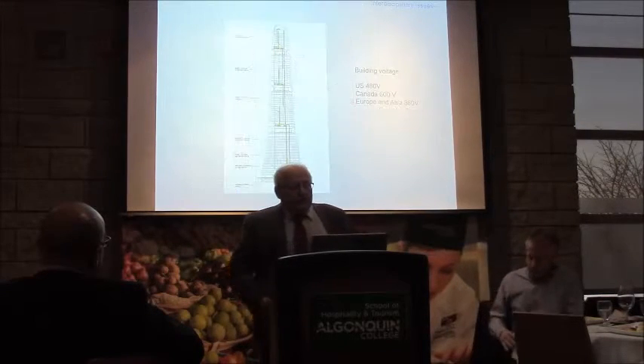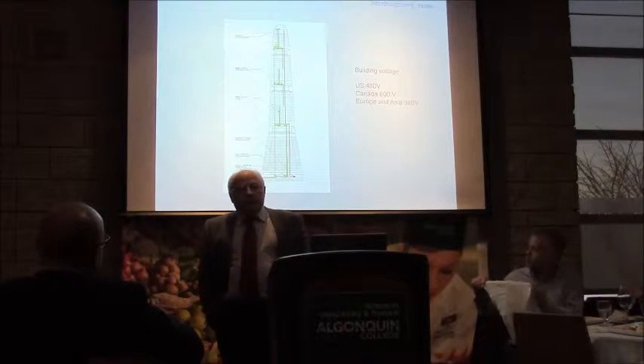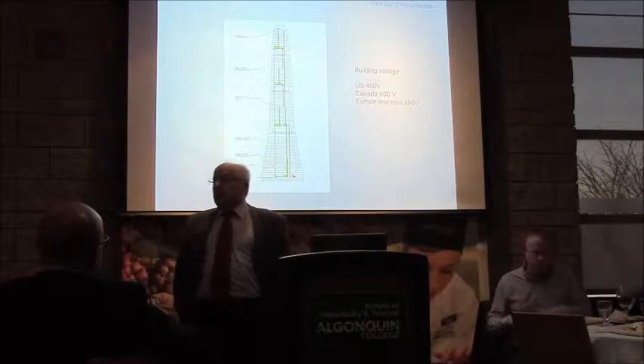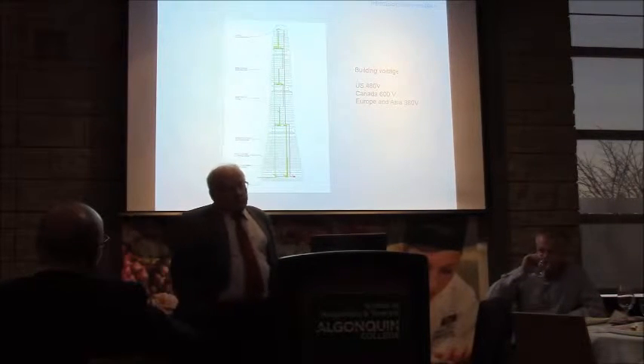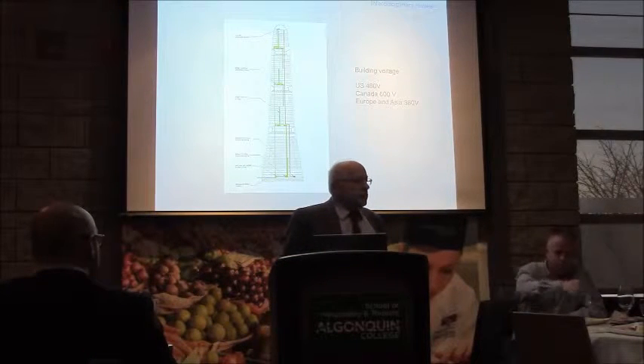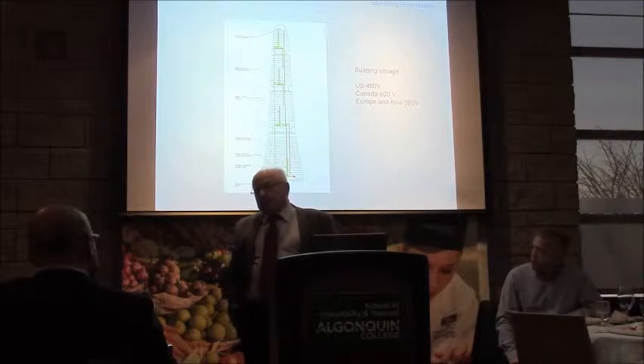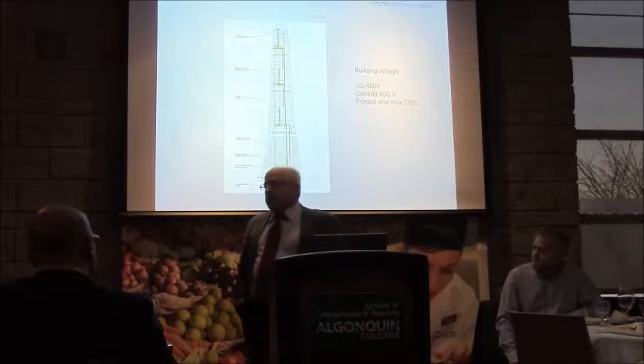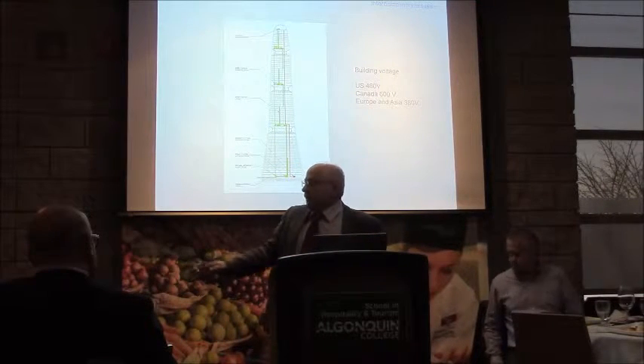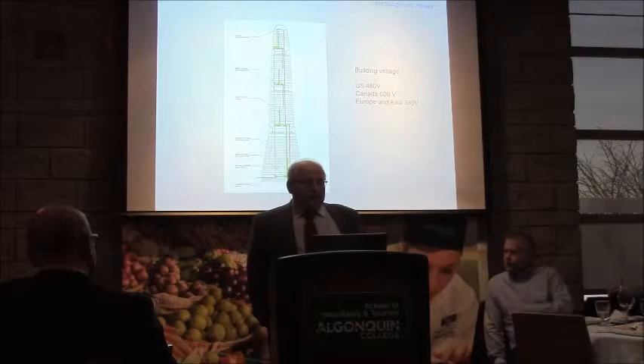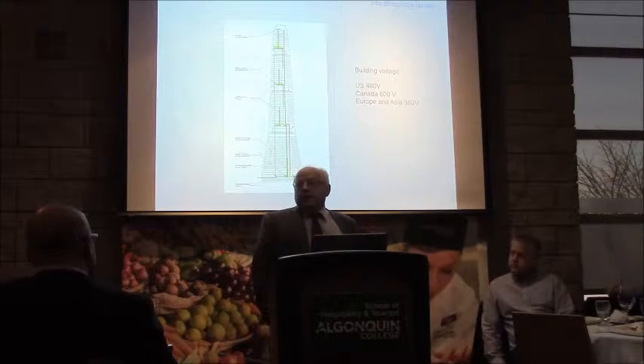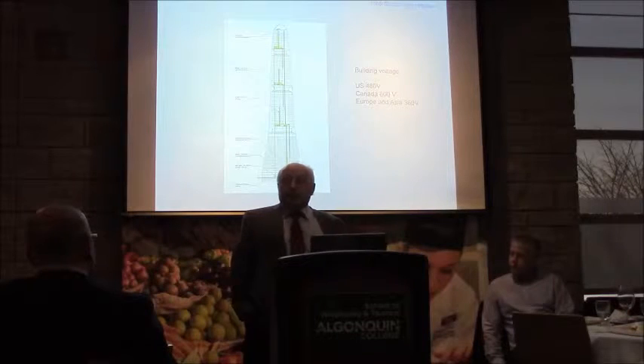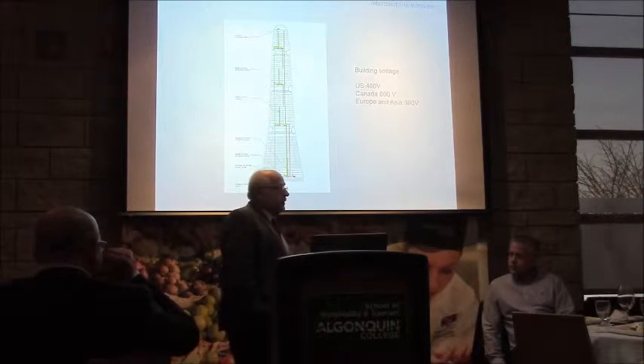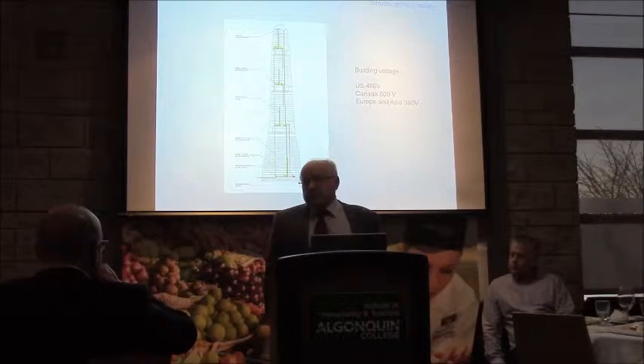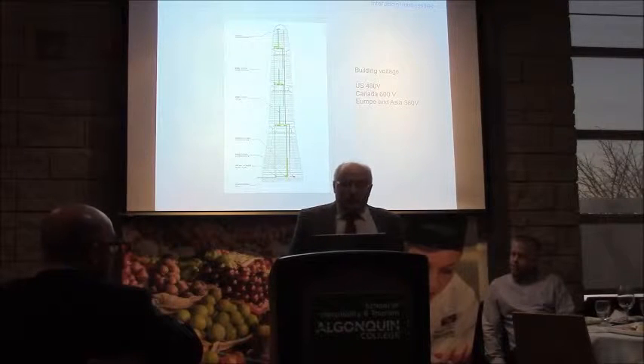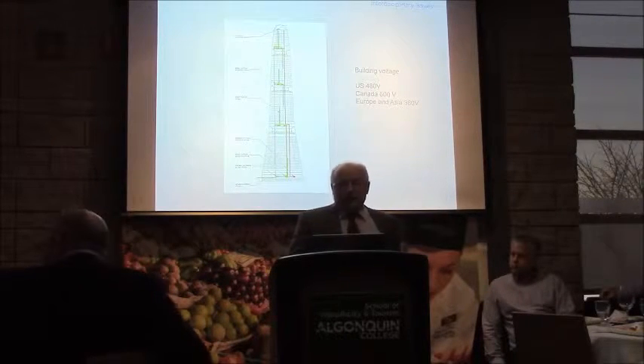Talking about coexisting, we have to live with Sparky as well. So power distribution is an interesting proposition in a big, tall building. While we typically imagine 600 volts as the number we deal with on buildings, many chiller plants will go with much higher voltages, particularly close to the transformer area, to minimize those kinds of costs. Voltage drop issues become a real problem, so we go with much higher voltages and have actual transformer stations buried within the taller buildings to transform down to operational voltages. That's an element we have to consider, live with, and accommodate as mechanical engineers.